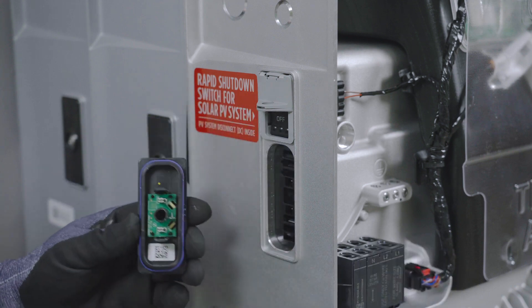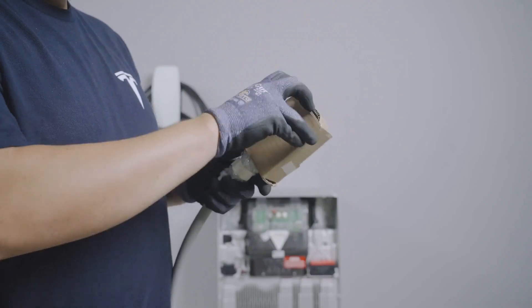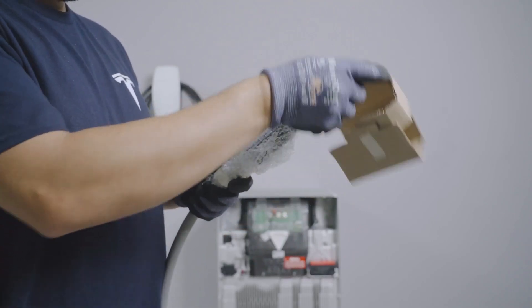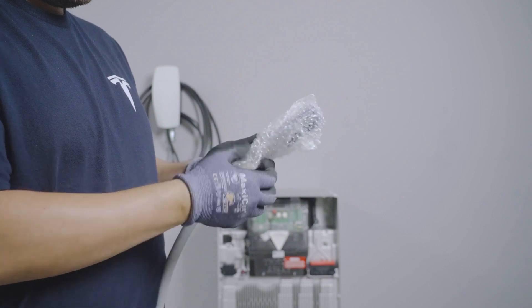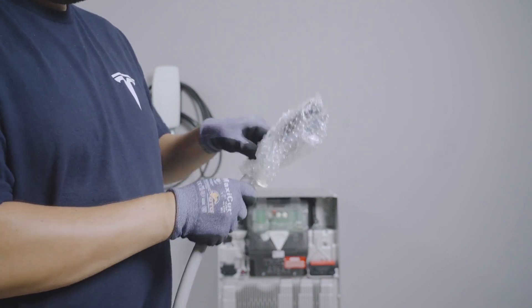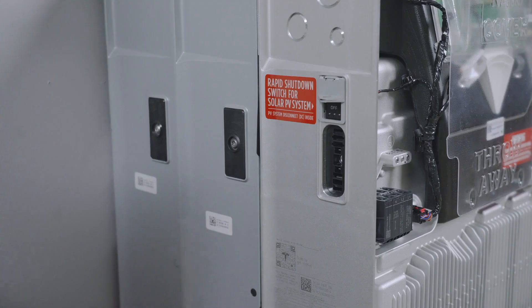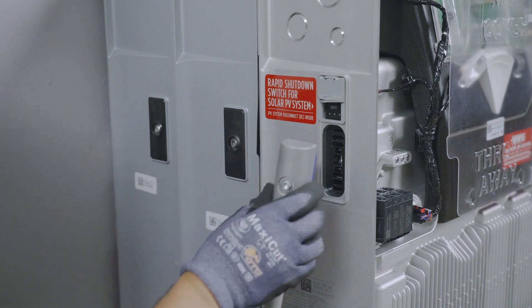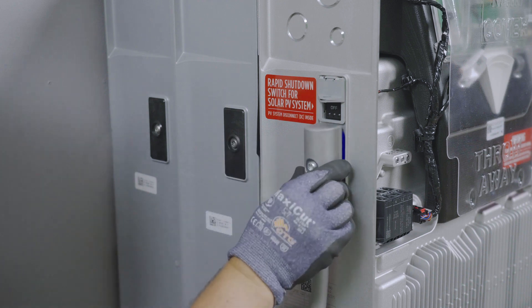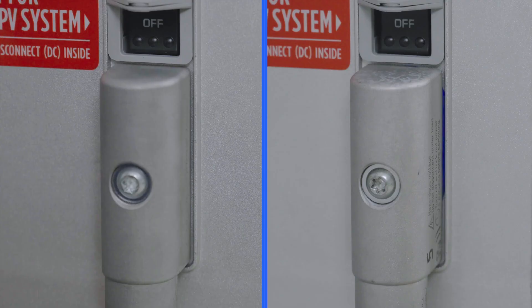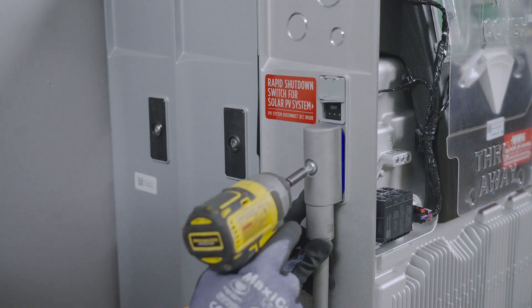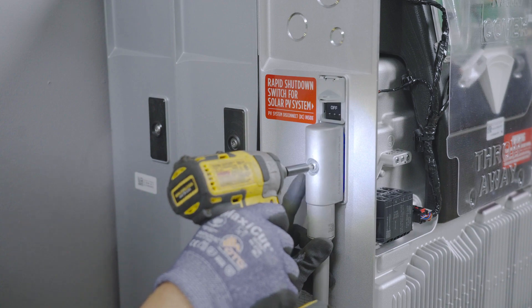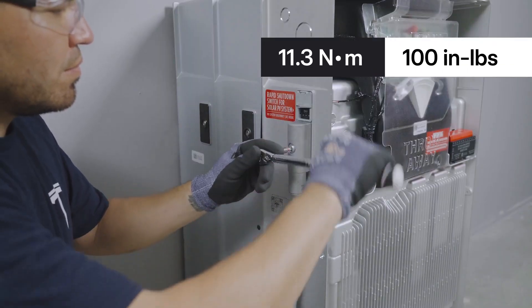Caution, do not remove this cover if exposed to active rain or snow. To prevent damage or debris, do not remove the protective cover from the wiring harness or the expansion port cover until ready to make connections. Remove the protective cover and plug the wiring harness into the expansion port. When fully seated in the expansion port, the rubber gasket around the connector will not be visible. Secure the connector to the port with the T40 screw and torque as specified.